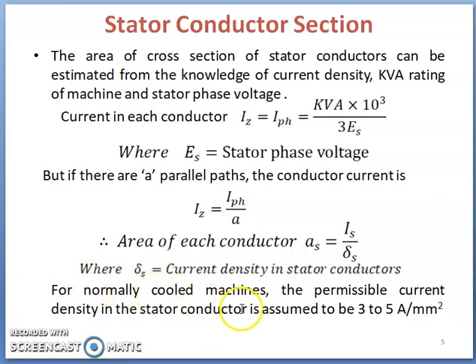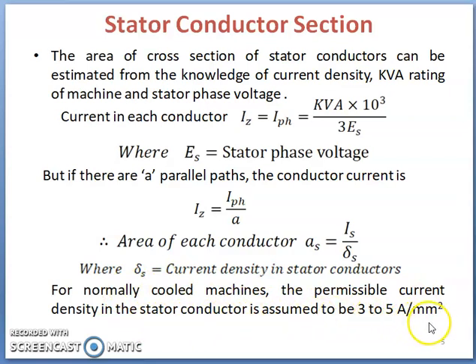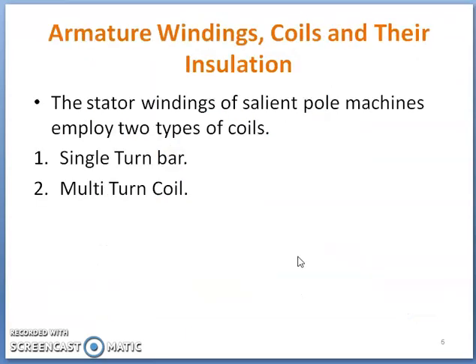For a normally cooled machine, the permissible current density in the stator conductor is assumed to be 3 to 5 ampere per mm squared. This is the procedure to calculate the cross-sectional area of stator conductors. We now move on to armature winding coils and their insulation.